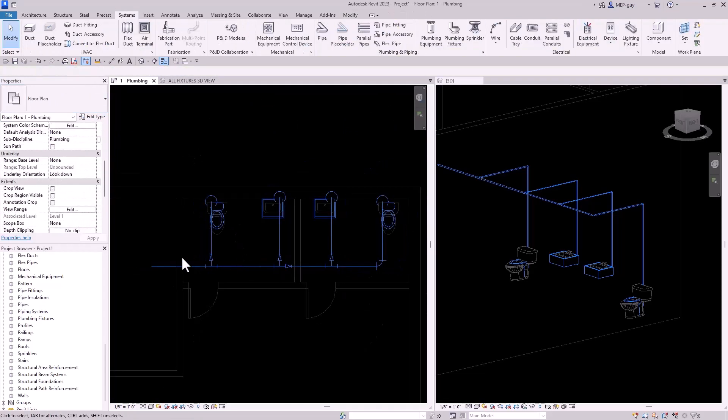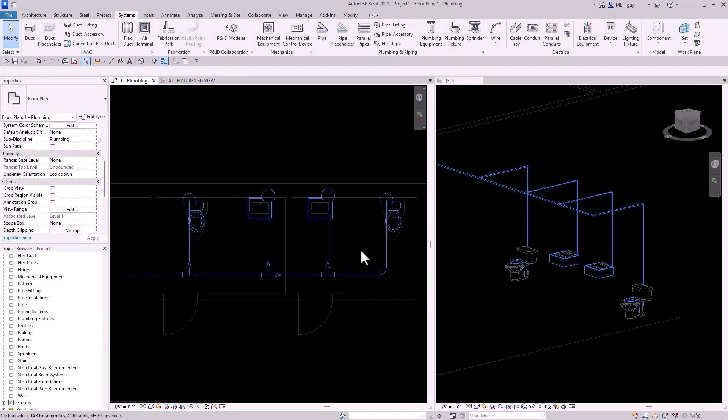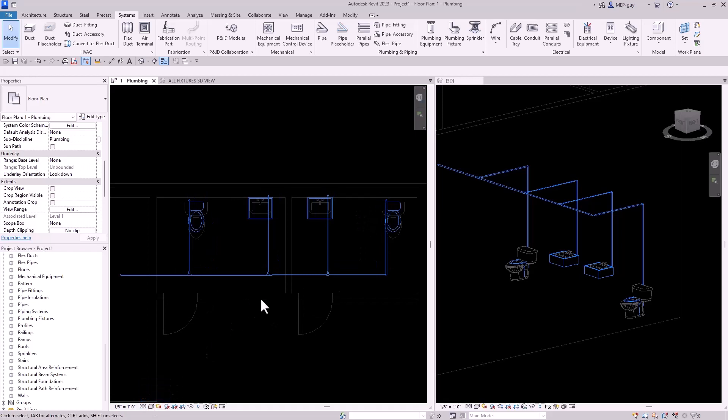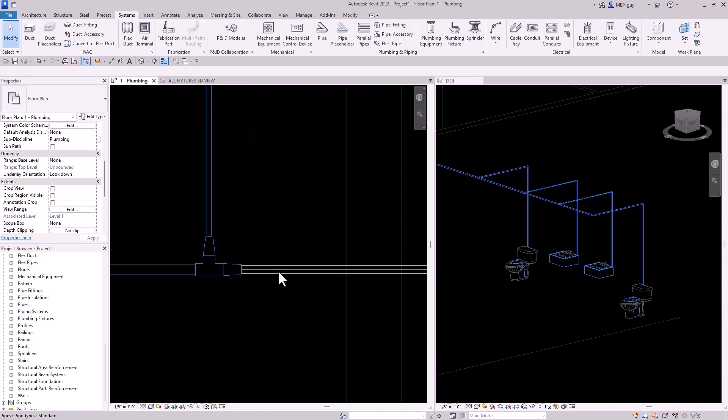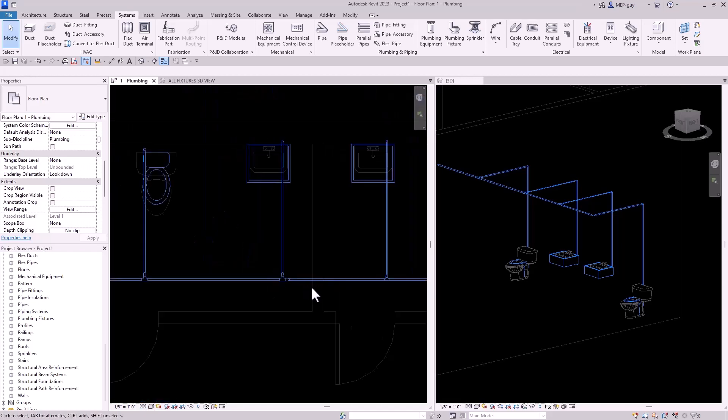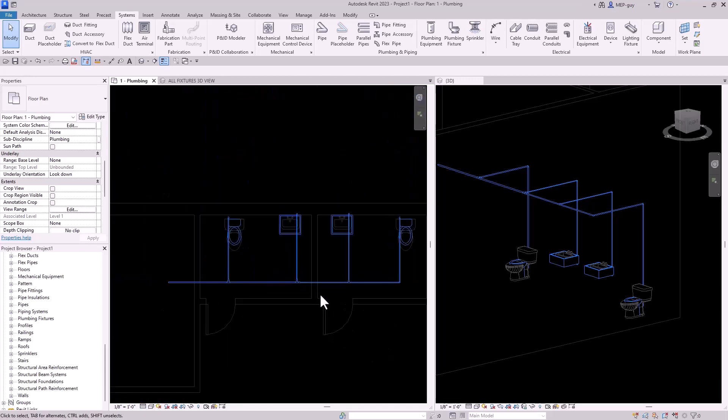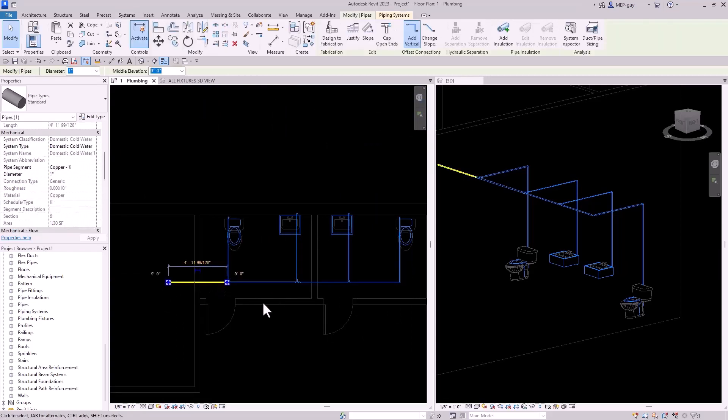And now you can see the little arrows are basically telling us that there's a transition happening here. And so you can see we're transitioning now from a one inch piece of pipe to a three quarter inch piece of pipe. So you can see Revit has automatically sized our piping for us. So we can actually look at that in a fine level of detail. And you can see Revit's already put in the fittings for us and everything's automatic.